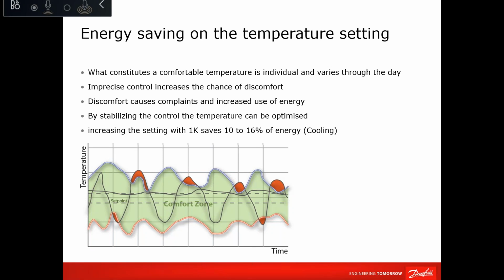And how this 10 to 16% can be proven, you can go to any heat load calculation program and size your unit with a unit set point of 23, for example, and then size it again with 22 and see the difference in MBH. And how do we convince the customer to do this?